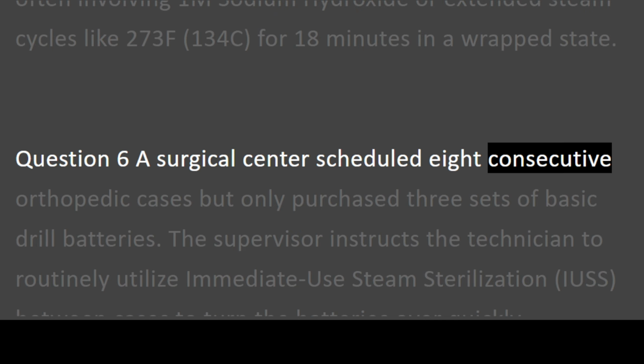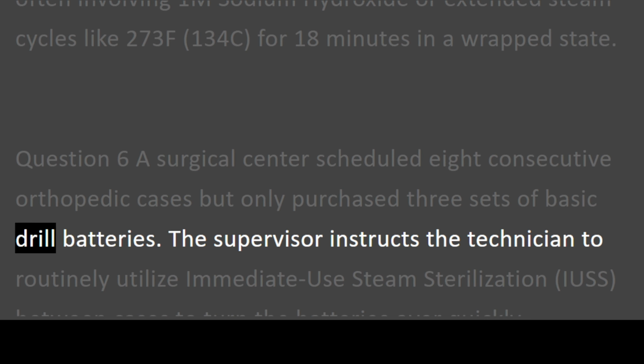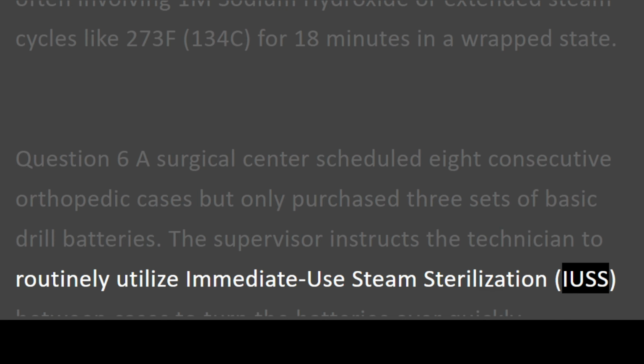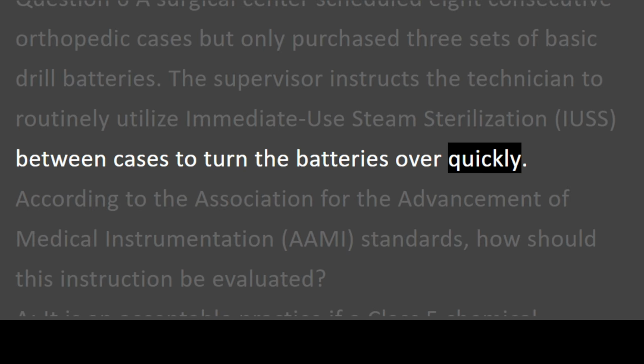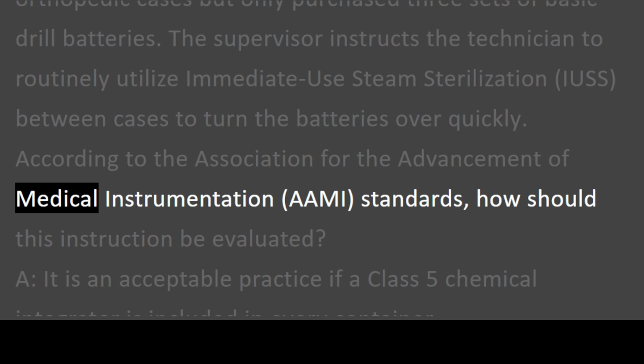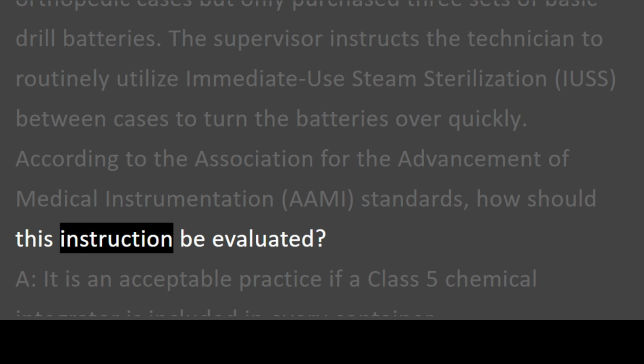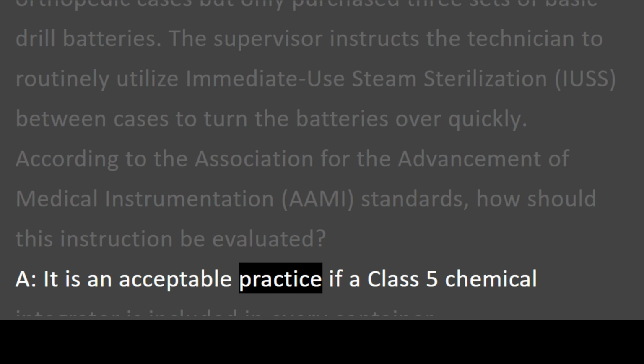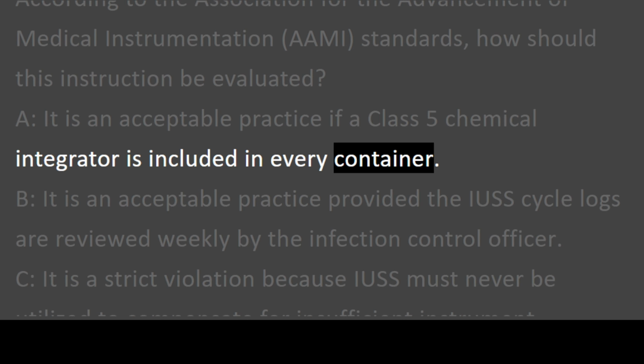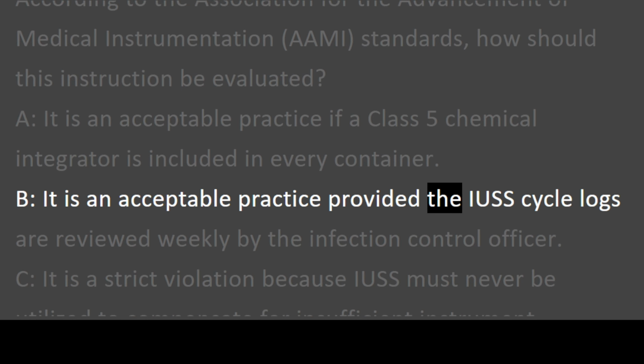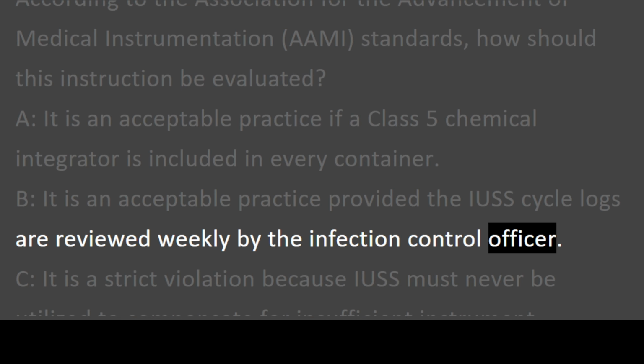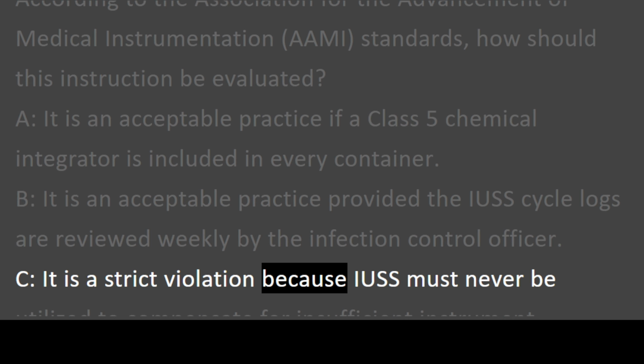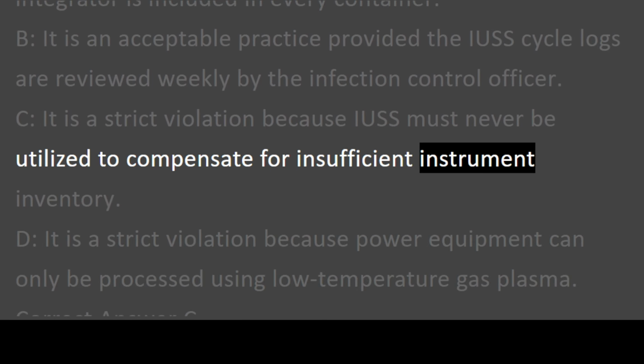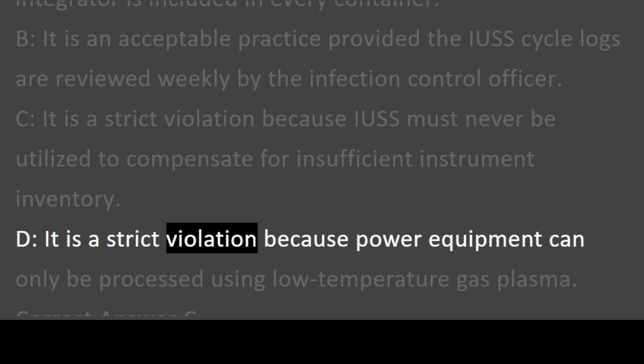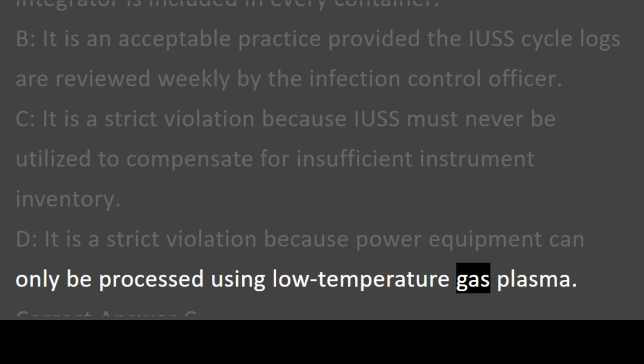A surgical center scheduled 8 consecutive orthopedic cases but only purchased 3 sets of basic drill batteries. The supervisor instructs the technician to routinely utilize immediate-use steam sterilization, IUSS, between cases to turn the batteries over quickly. According to the Association for the Advancement of Medical Instrumentation, AAMI, standards, how should this instruction be evaluated? A. It is an acceptable practice if a Class 5 chemical integrator is included in every container. B. It is an acceptable practice provided the IUSS cycle logs are reviewed weekly by the infection control officer. C. It is a strict violation because IUSS must never be utilized to compensate for insufficient instrument inventory. D. It is a strict violation because power equipment can only be processed using low-temperature gas plasma.